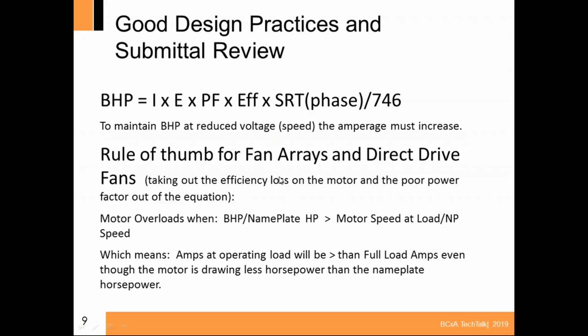So I have a rule of thumb that I use when I look at the submittals and design requirements: the motor overloads when the brake horsepower divided by the nameplate horsepower is greater than the ratio of the speeds on a one-to-one basis. So for instance, 9 divided by 10, the 9 horsepower and the 10 horsepower, and the speed 1140 divided by 1750. Well, the ratio is greater than the motor speed at load divided by the normal nameplate motor speed. So at that point, it overloads, and I've seen it happen multiple times. Your vendors are not perfect. The vendors that supply these will do crazy things sometimes.